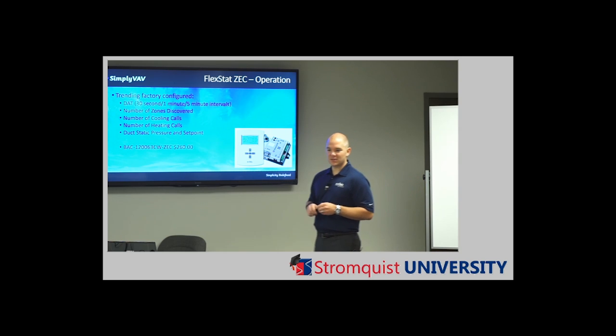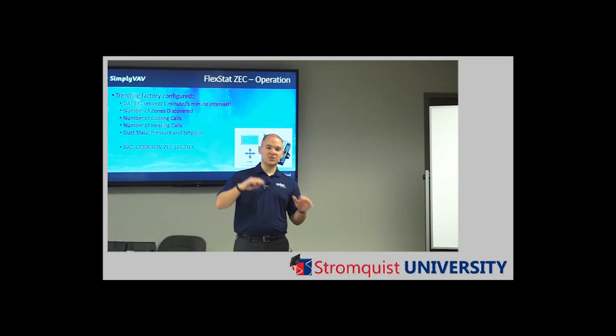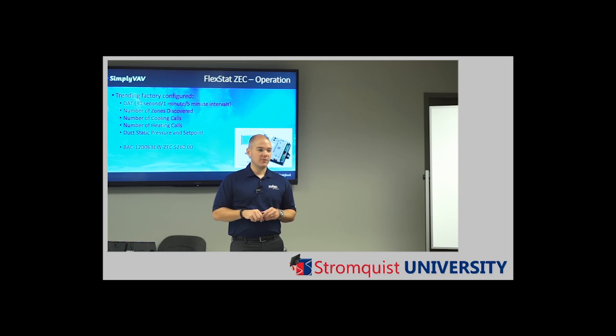The greatest example I always use, I think, is of two conference rooms. One has 2 guys, one has 8 guys. They're both equally sized, so they're both designed for maximum load. If it's pressure dependent, the conference room with 8 guys is going to eat up all the air that air handler can put out. The room with 2 guys is going to become satisfied very quickly, close its box. All that air now is going to be pushed into the conference room with 8 guys, and it's going to subcool that space very quickly, probably faster than the stat can catch up. So now they're going to be uncomfortable.